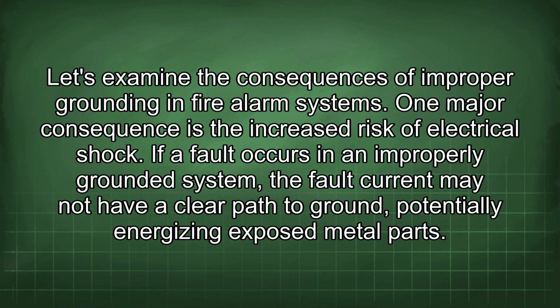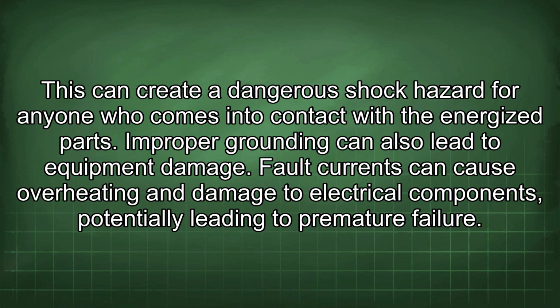Let's examine the consequences of improper grounding in fire alarm systems. One major consequence is the increased risk of electrical shock. If a fault occurs in an improperly grounded system, the fault current may not have a clear path to ground, potentially energizing exposed metal parts. This can create a dangerous shock hazard for anyone who comes into contact with the energized parts. Improper grounding can also lead to equipment damage. Fault currents can cause overheating and damage to electrical components, potentially leading to premature failure.